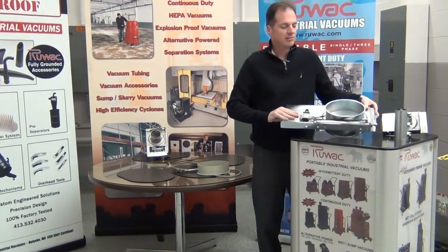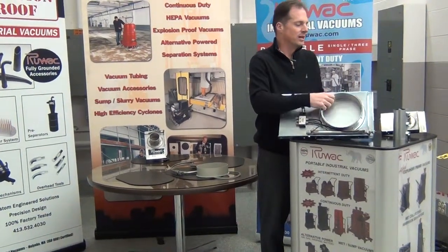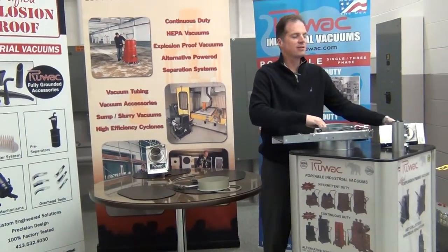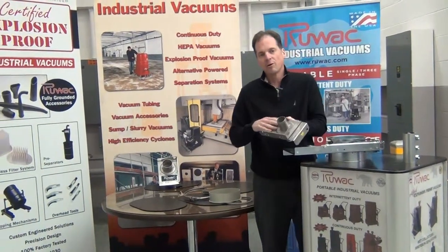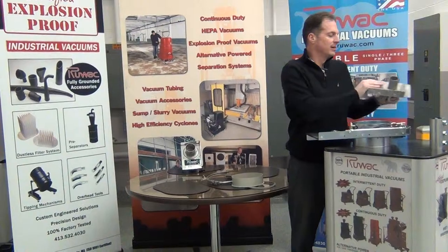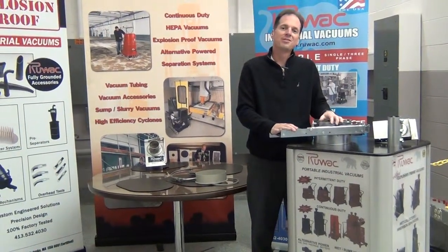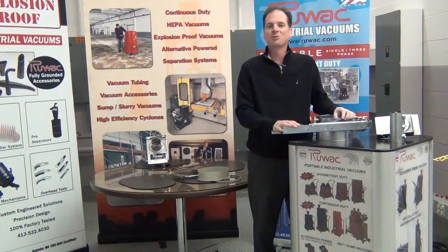Don't forget you're going to need these clamps for either side of the blast gate where you're connecting to. You cannot weld directly to the blast gate because that would affect the gasket that's inside of this airtight chamber. This has been a review of Ruwac airtight blast gates for use with vacuum systems up to 16 inches of mercury.